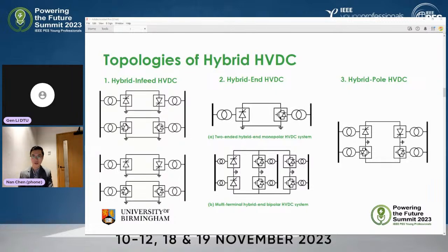The third type of the hybrid HVDC will be hybrid pole HVDC. It's majorly applied to bipolar HVDC. So for example, one pole is utilizing the LCC HVDC, another pole is using the VSC HVDC or MMC HVDC. The next page, please.